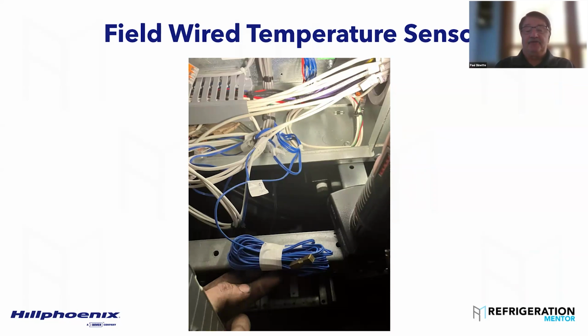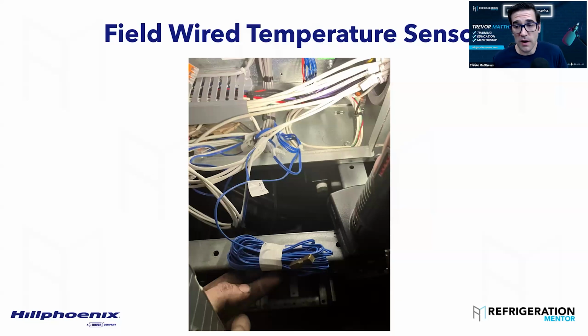So how was that going to control? During the day, it was trying to go supercritical because the temperature probe was reading 100 degrees. So these sensors that ship loose are rolled up in the cabinet. They're on the prints as field mounted, and have to be mounted by the contractor. Okay. And so this is already wired up. It makes it even easier too. You just have to go and mount it.